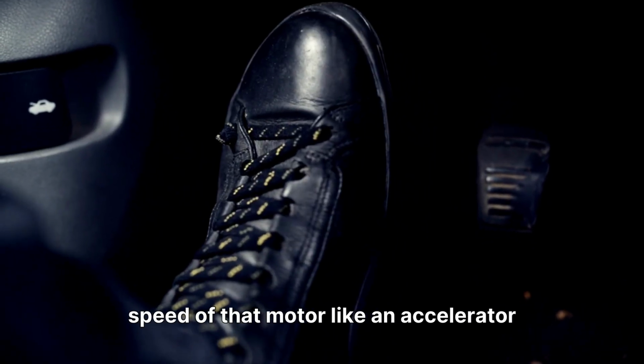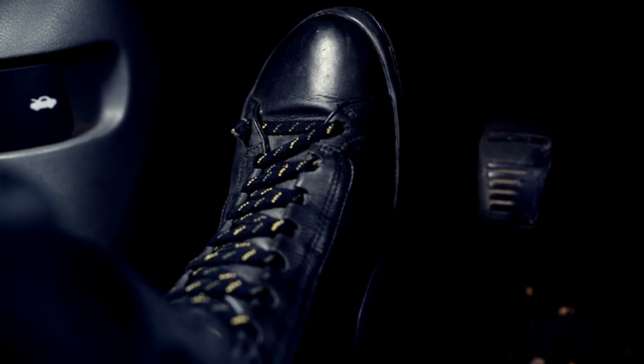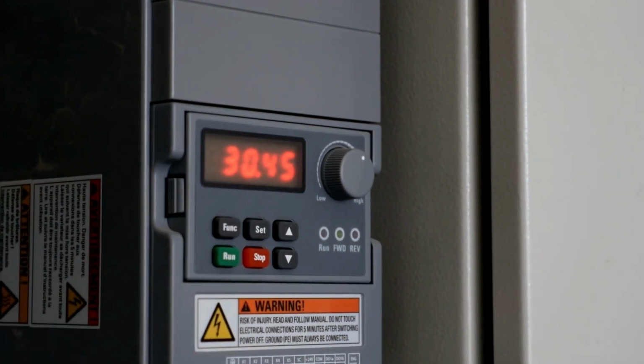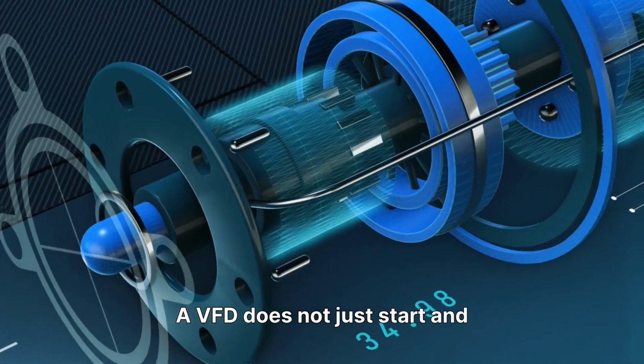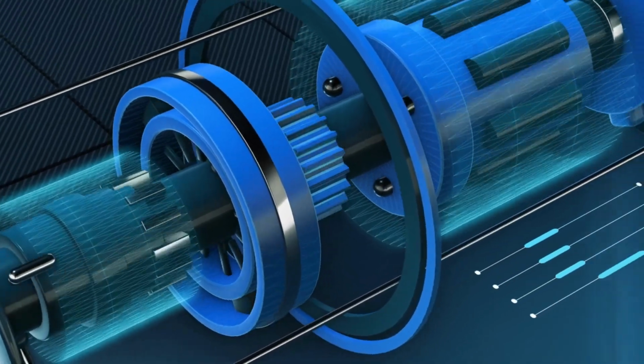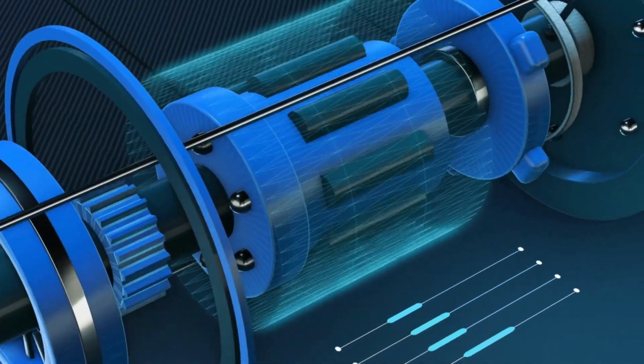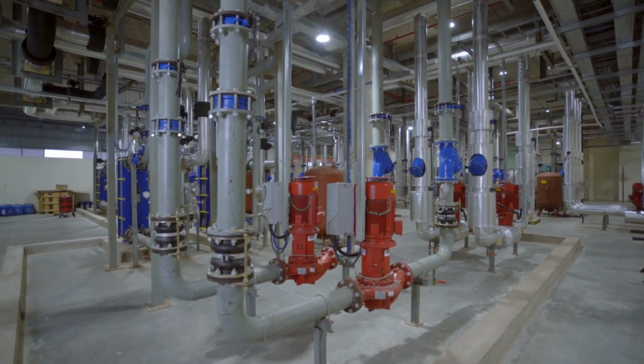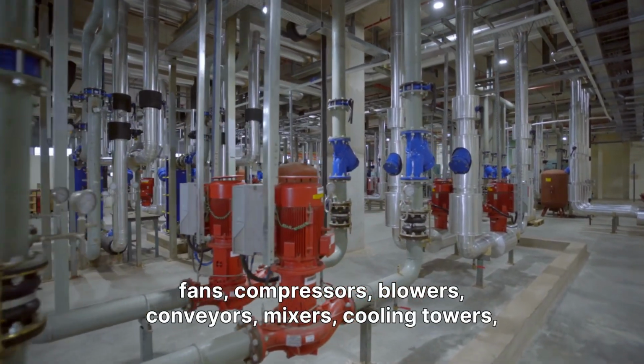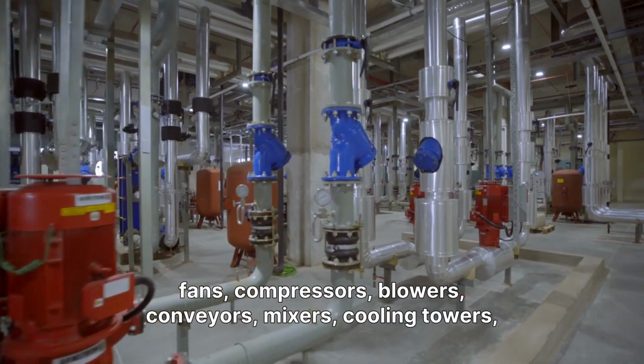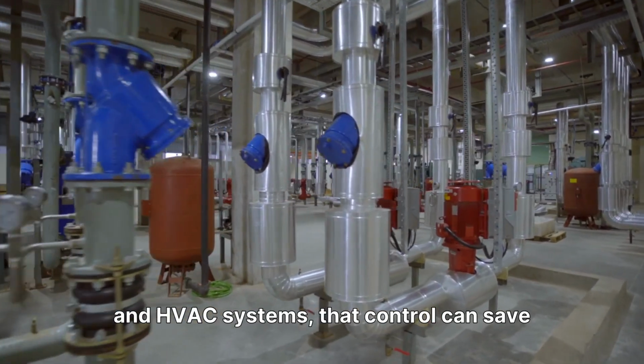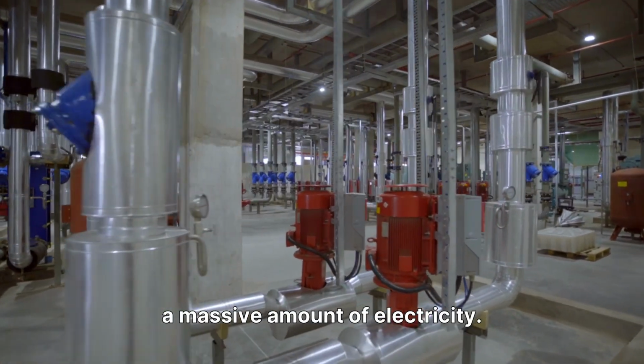Now imagine one device quietly controlling the speed of that motor like an accelerator pedal controls a car. That device is called a VFD, variable frequency drive. A VFD does not just start and stop a motor, it controls how fast the motor rotates. And in industries where motors run pumps, fans, compressors, blowers, conveyors, mixers, cooling towers, and HVAC systems, that control can save a massive amount of electricity.